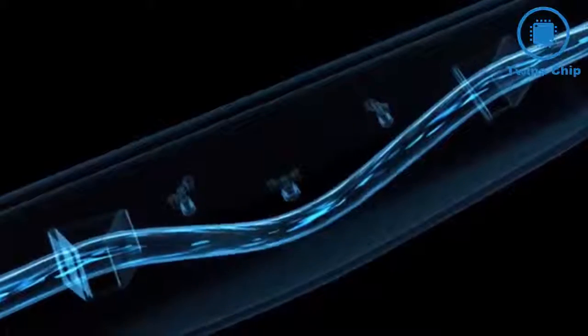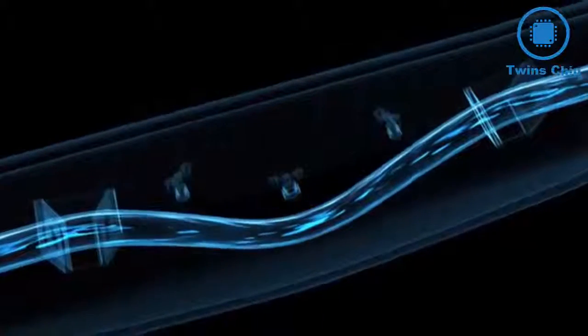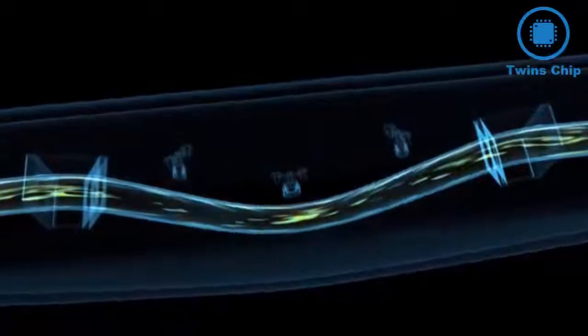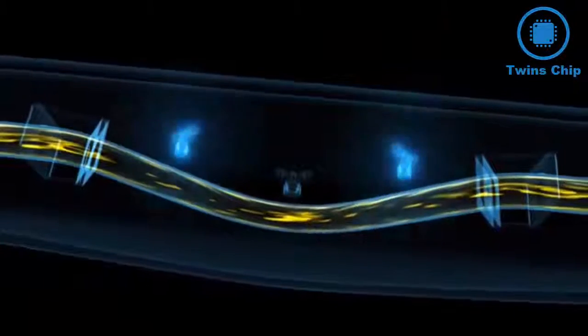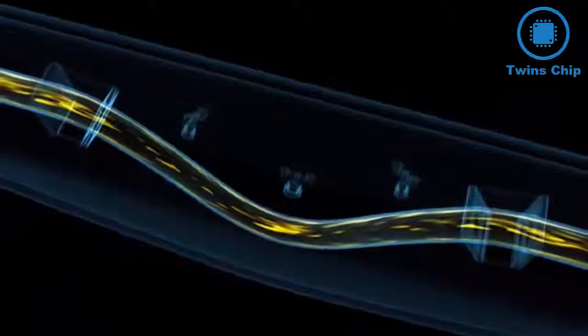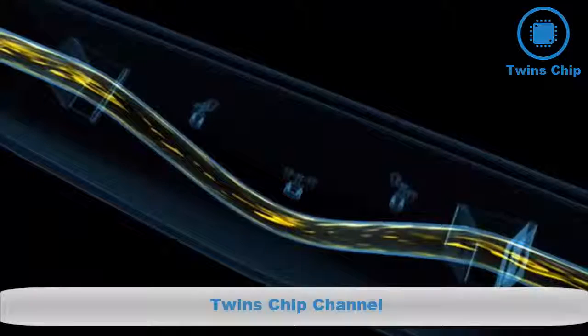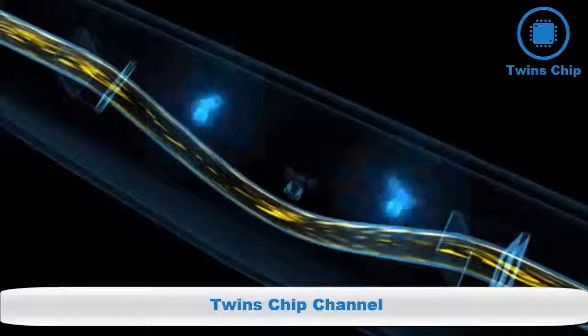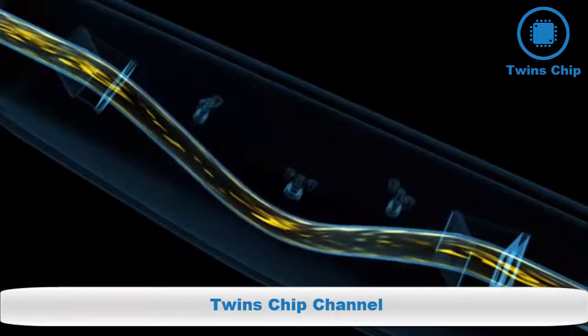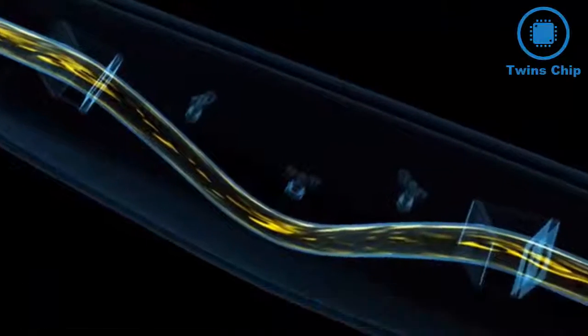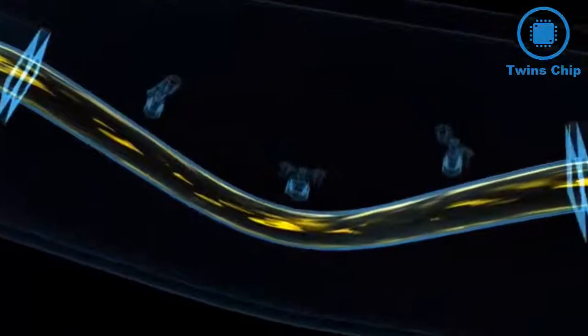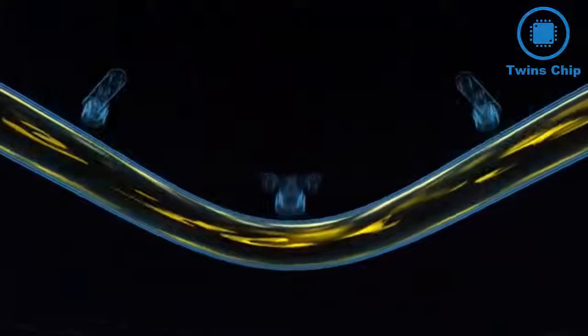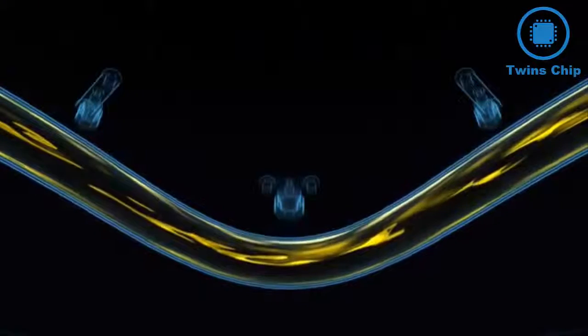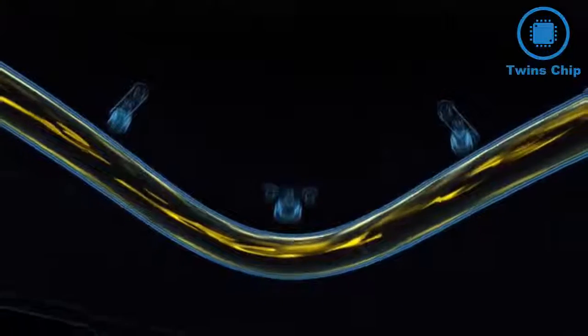From the animation, it's clear that a tube filled with water oscillates more frequently than a tube filled with honey, for example, which has a far higher density. Thus, the oscillating frequency is a direct measure of the fluid's density. Both the density and the flow are determined simultaneously but independently via the tube oscillation.